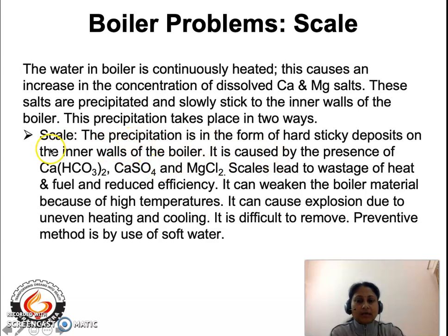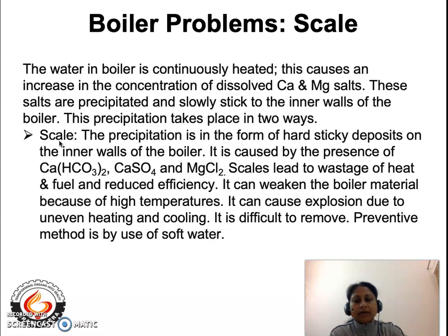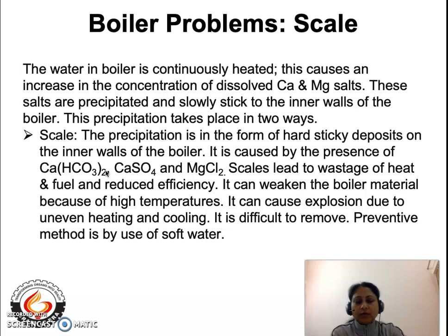Scales are caused by the presence of calcium bicarbonate, calcium sulfate, and magnesium chloride. When calcium bicarbonate is heated at high temperature, it converts to calcium carbonate — the most insoluble precipitate — which sticks firmly to the inner walls of the boiler. For calcium sulfate, as temperature increases its solubility decreases, so it also deposits as a very hard scale on the inner walls.